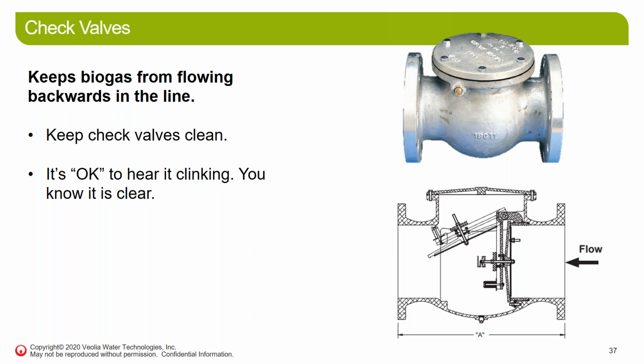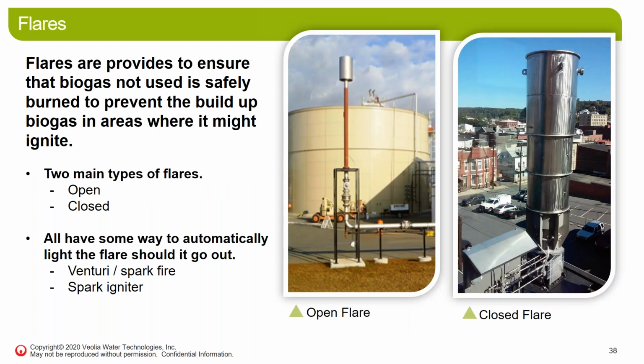Check valves are typically a key component in our system, keeping gas from flowing backwards in the line, or air coming back in if you have a flare, open flare, or other piece of equipment. So again, make sure these things are clear. Typically, you can hear these valves opening and closing during operation, so it's okay if you hear that clinking. But we've seen these things freeze, we've seen them get clogged, so it's a restriction. So you should check this during an outage.